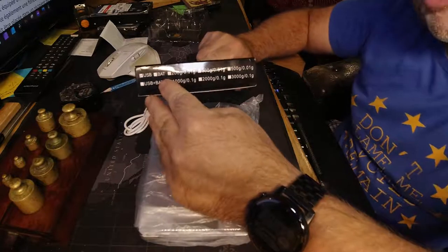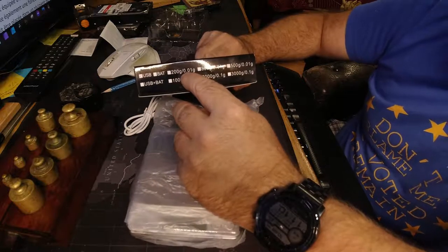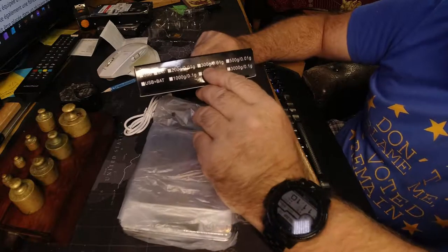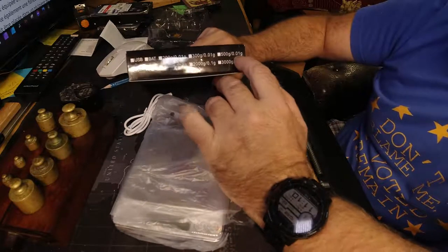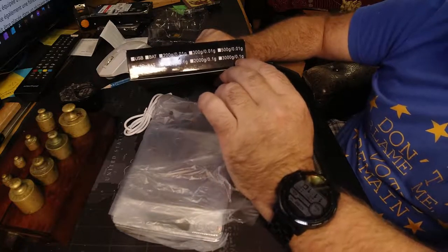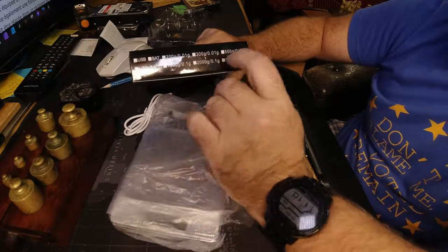It can actually weigh a higher weight than some of the other versions they do. If you look on here, they do a USB or battery version. They do a 200g model down to increments of 0.01 of a gram. Then they have a 300g model and a 500g model with pretty much the same accuracy. But when you get to the higher scale such as this 3000g model, it's 0.1 of a gram on the 1000g, 2000g, and 3000g models.